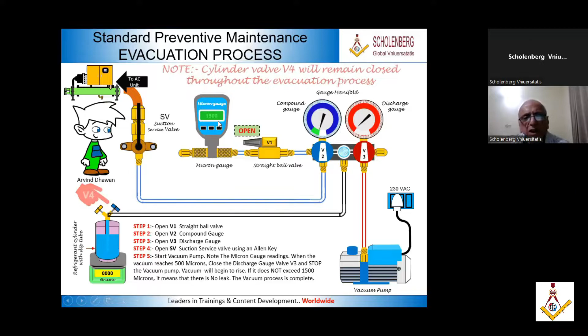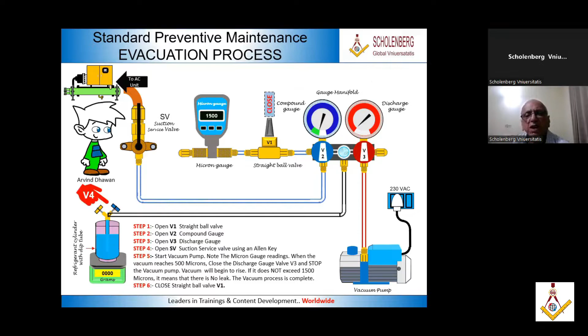Now, let's take a look at this. 10,000 now, 5,000, 1,000, 500. Now close this valve. Close this valve, right? Stop the vacuum pump. The vacuum will rise. If it does not exceed 1500 microns, then it is okay. Then you close this valve and the vacuum process is complete.